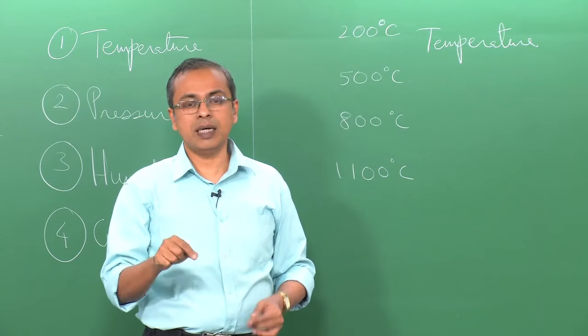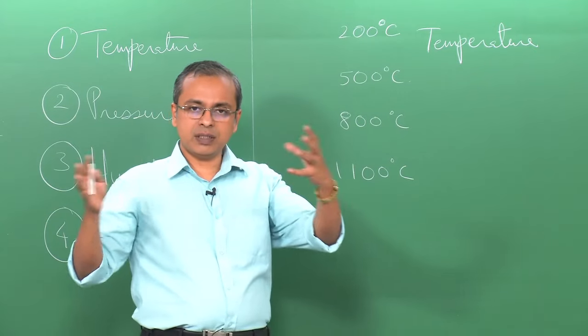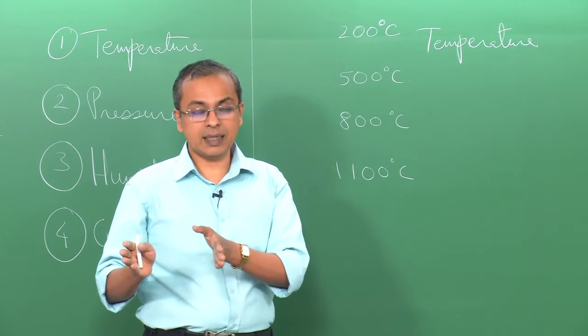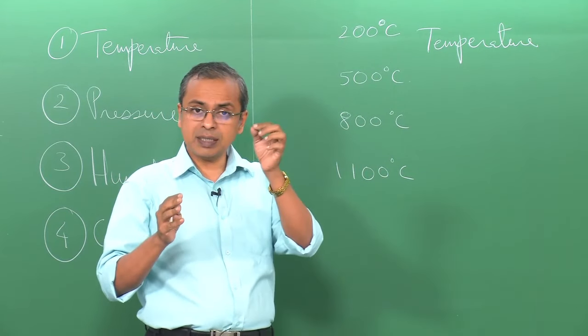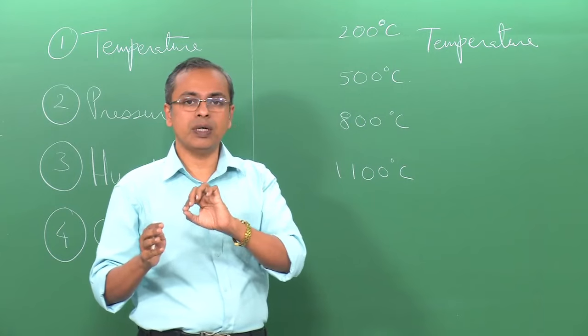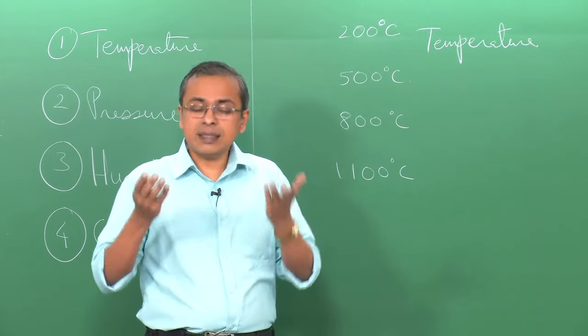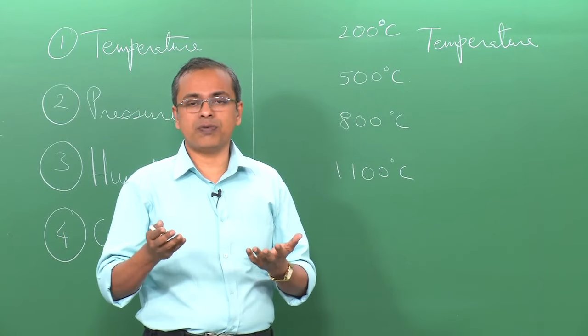That is very important, because you can have a situation where the sensor is located at one location, your sample is located at another location, and therefore, the temperature that the sensor is reporting to you is not the temperature at which your sample is sitting. Okay. And this is an experimental thing that you have to be aware of, right.